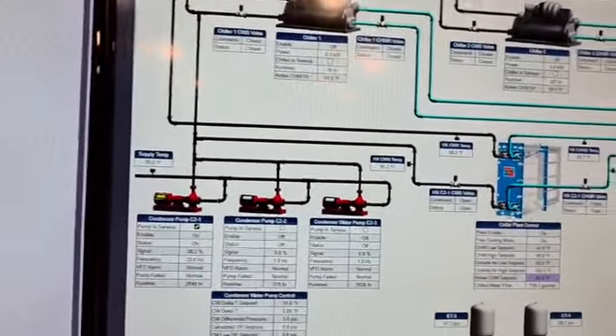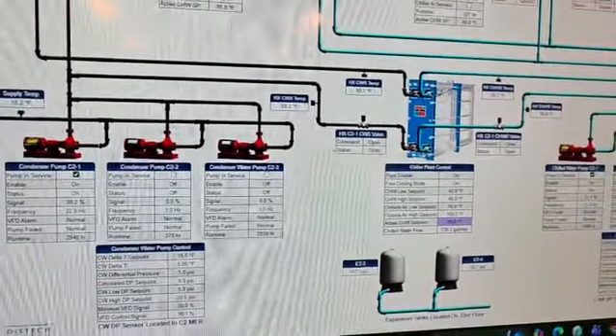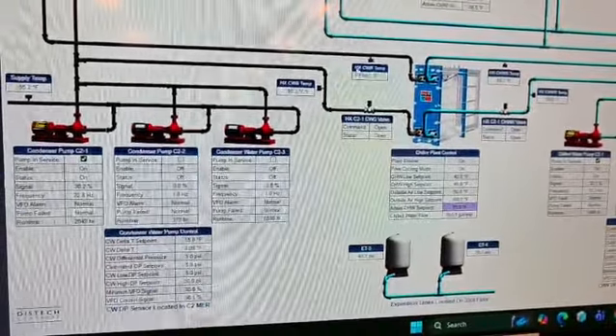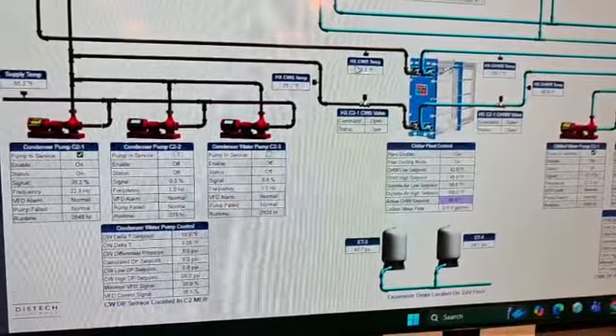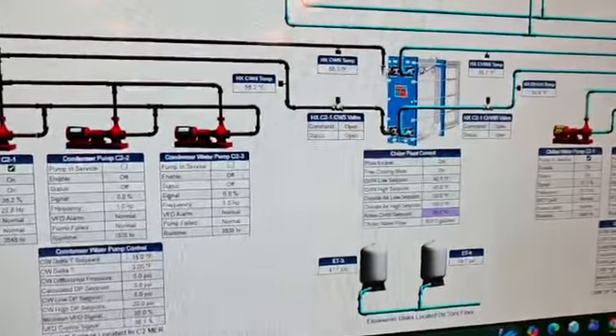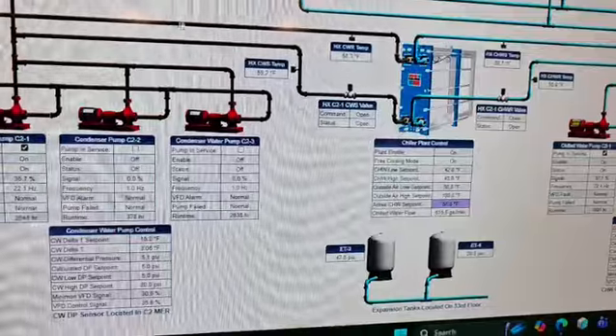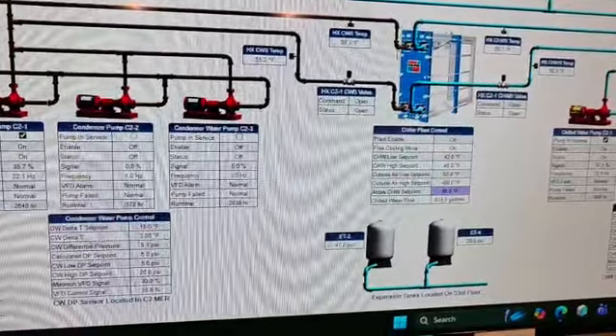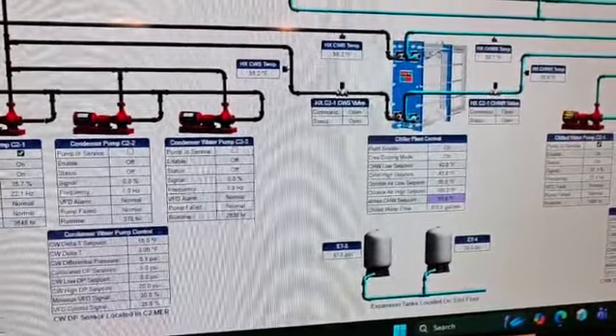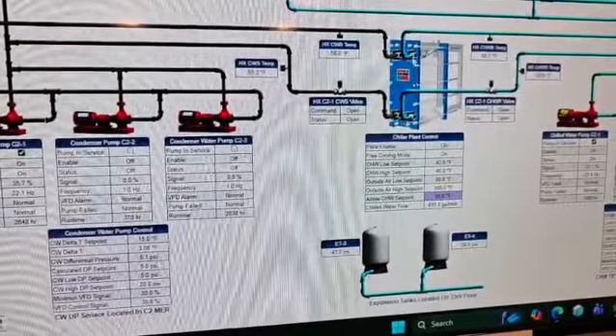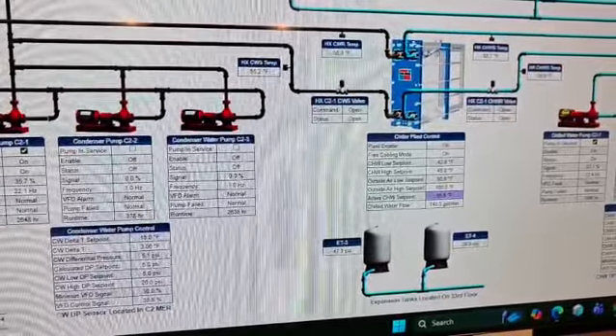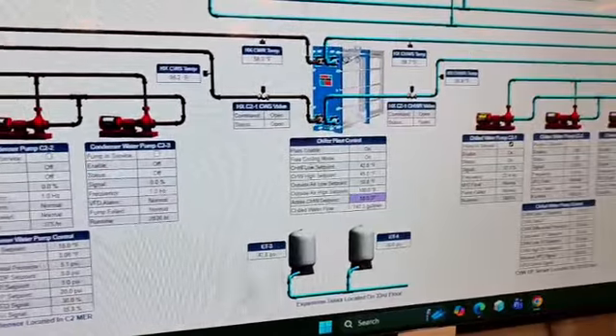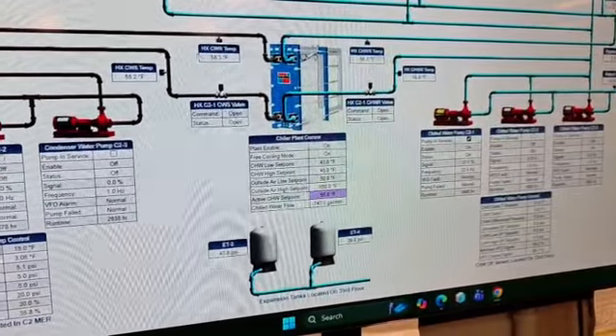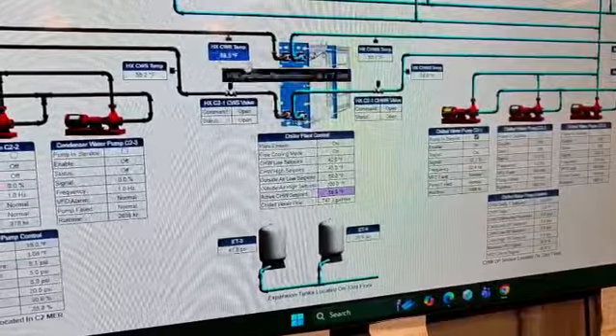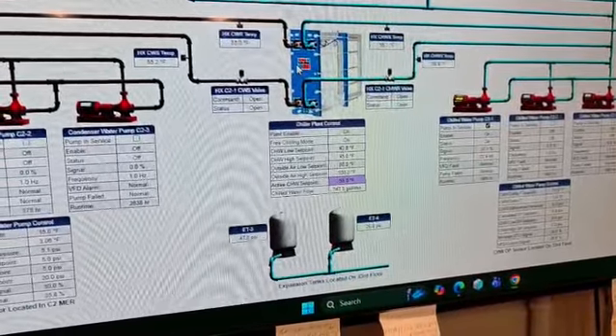So what you do is use this device, which is called a heat exchanger. That's what it is, the HX, heat exchanger, right? And it's the same logic, right? The water from the cooling tower gets into it, actually coming from the bottom. It comes from the bottom, goes inside, and goes back to the cooling tower. And this is the water that you're running through the building, right? There's almost no exchange. You see 57, 58, because the cooling tower water is good enough.